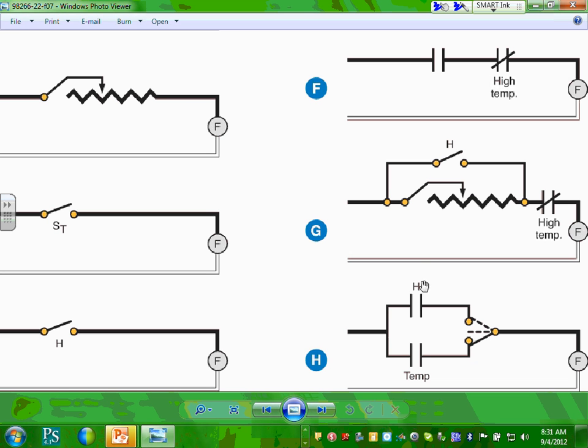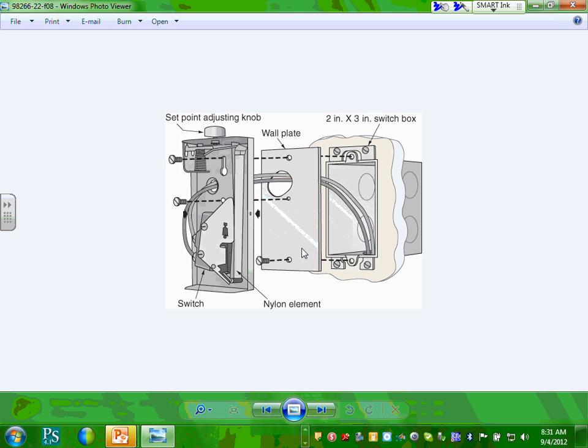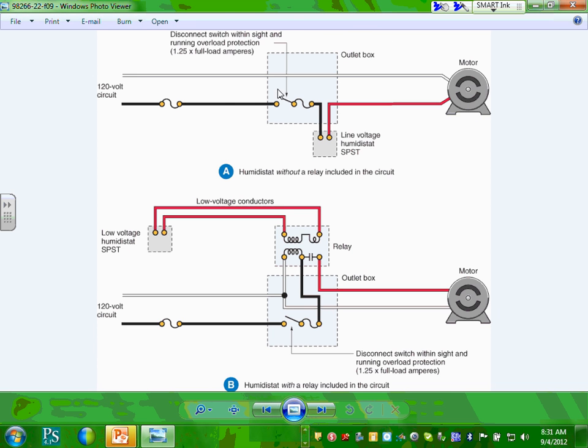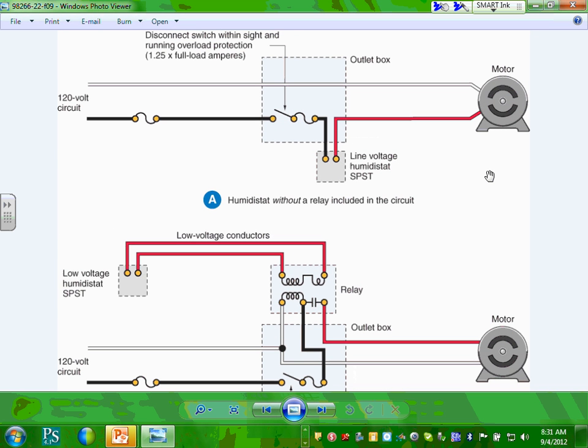I'm going to show you a couple of these. This is how they do the control, and how you bring your wiring into a box controller and so forth. Here's my favorite. This happens to be a humidistat without a relay. They call it a line humidistat or line temperature control. Very similar, guys. Do you see the disconnect? I told you they come with an off position that qualifies as a disconnect. In this application, Darren, remember the baseboard heater that you did in your project? That's exactly what you're typically going to do: either have a box like this or a built-in controller.